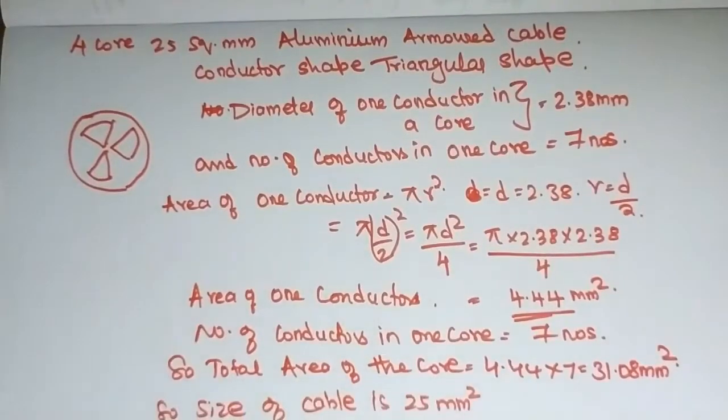You may have a doubt that it may be due to the difference between copper and aluminum conductors, because in the previous case we took a copper conductor and now we are taking an aluminum conductor. It is not because of that, it purely depends upon the shape of the conductor, because we took around 6 to 7 tests with round type aluminum conductors also. As the video would become very lengthy, we have shortened our calculations, and shown 2 examples here. If you have such doubts, in the same way you can check for those conductors also, and you will find the same results. And now we will see what voltage grading is.